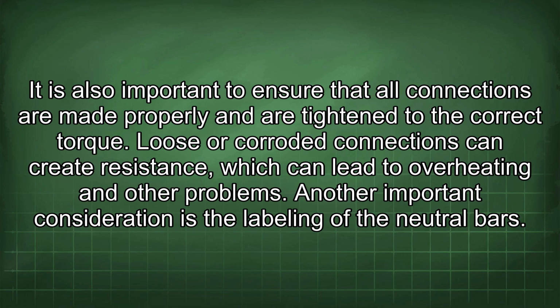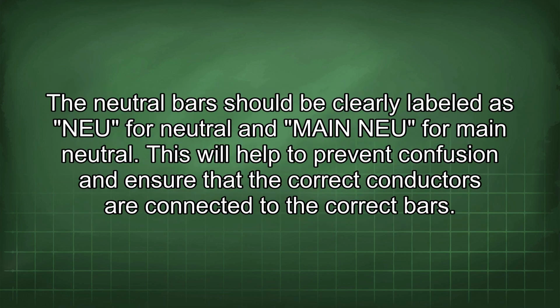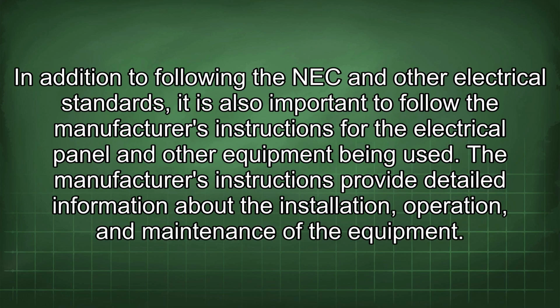Another important consideration is the labeling of the neutral bars. The neutral bar should be clearly labeled as NEU for neutral and main NEU for main neutral. This will help to prevent confusion and ensure that the correct conductors are connected to the correct bars. In addition to following the NEC and other electrical standards, it is also important to follow the manufacturer's instructions for the electrical panel and other equipment being used. The manufacturer's instructions provide detailed information about the installation, operation, and maintenance of the equipment.